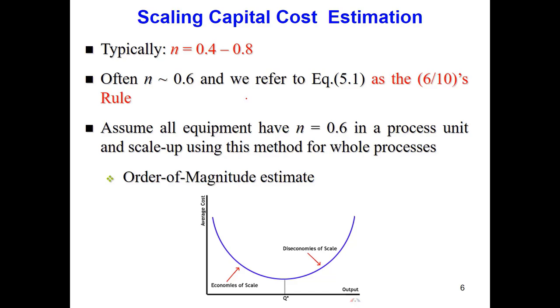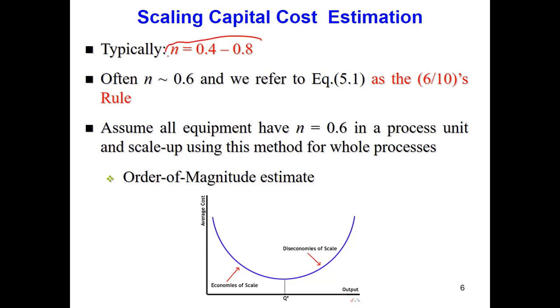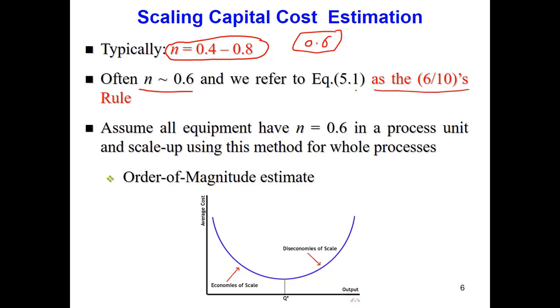n is usually between 0.4 and 0.8, and a value of 0.6 is a very typical value used in many industries and many places. When we use 0.6, it is called the six-tenths rule, or the 0.6 rule.